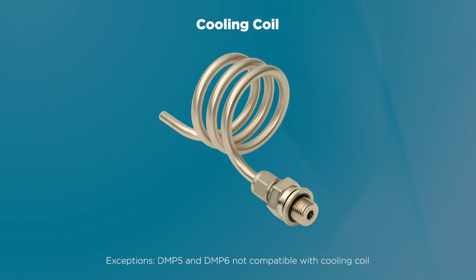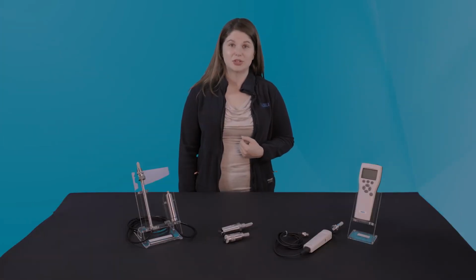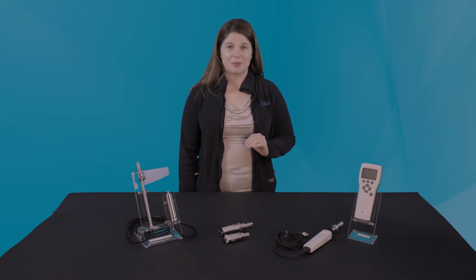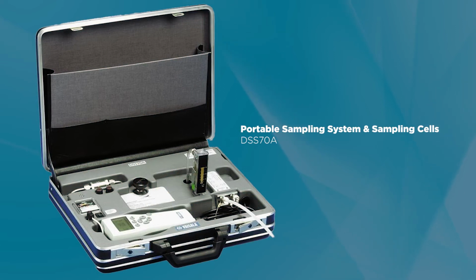When measuring moisture levels in hot air in a non-pressurized system, you also need a way to pull gas out of the application so that it can be cooled and then measured, since you can't rely on the system pressure for this. For these demanding applications, we offer the DSS-70A portable sampling system, which includes a pump and sampling system and can be paired with our portable DM70 meter that I'll discuss next. The DSS-70A system can also be handy for any low-pressure application, such as plastics drying, or applications with no suitable ports to allow for in-process measurement.